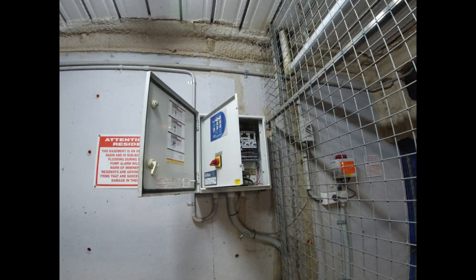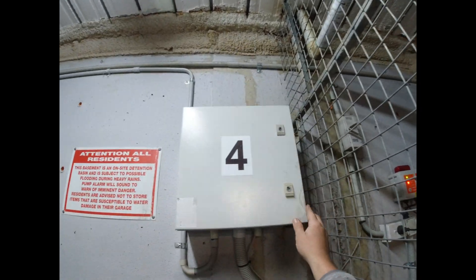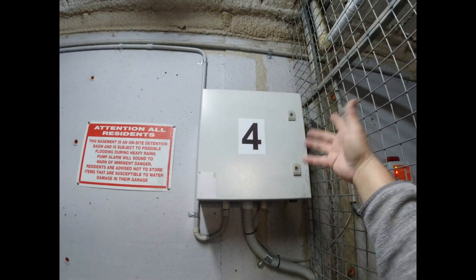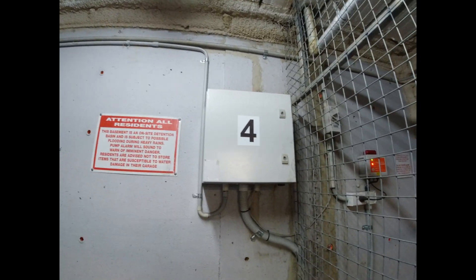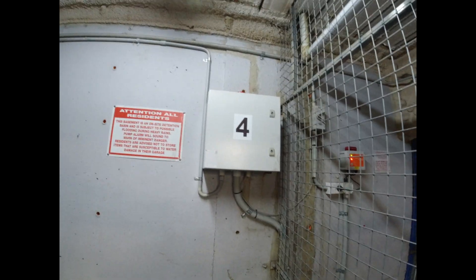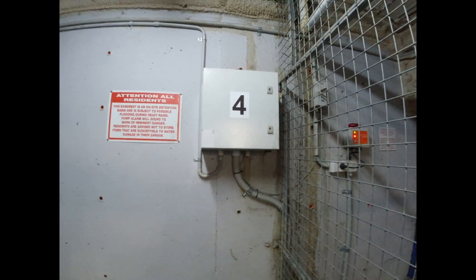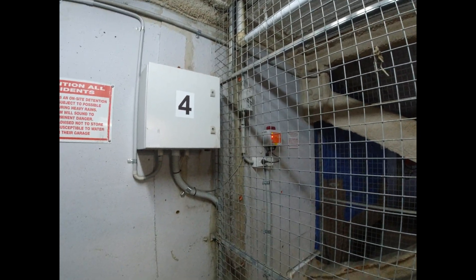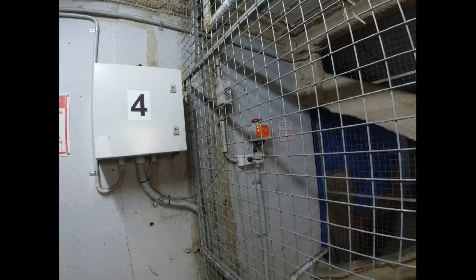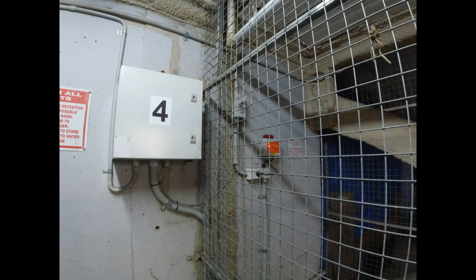What we have here is a power switchboard pump. I've had to open it up — the main reason we're putting a lock on it today. It comes with these little tiny catches that you can open with a screwdriver or a pair of flat blades. The problem is it's been tampered with, and when it gets tampered with or the alarm goes off and people just turn it off to shut it up, the basement will fill up with water — and that's pretty much what did happen. You've got a liquid level alarm over there, a green for power, and a red for it being full.